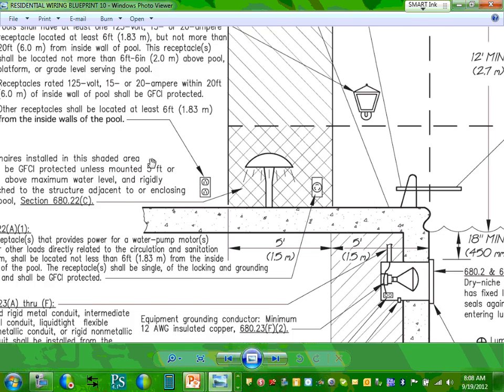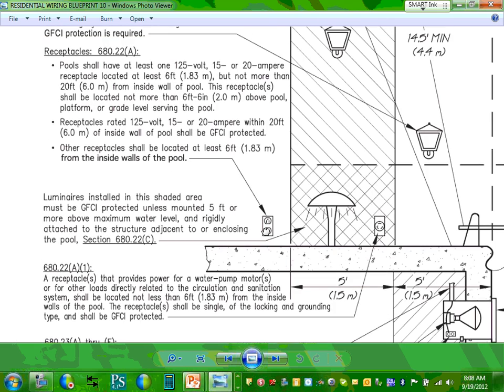I'm going to bring up the receptacle, guys. Can you guys see your receptacle right here? The pool shall have at least one receptacle. Do you guys remember what I told you, that you have to have at least one receptacle, 120 volt, 15 or 20 amp? The receptacle cannot be installed closer than 6 feet from the swimming pool or further than 20 feet. And it has to be GFCI. Can you have a thumbs up, Chad? One receptacle, not closer than 6, not further than 20 feet, GFCI. That's the requirement for your receptacle.